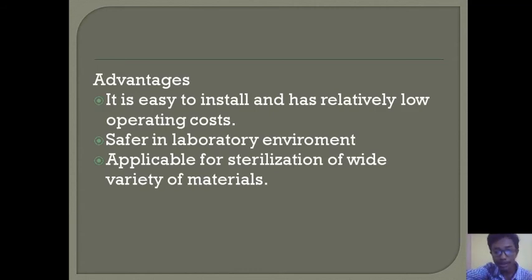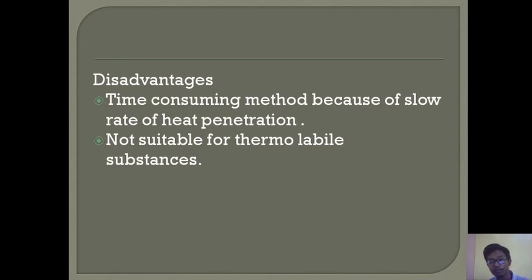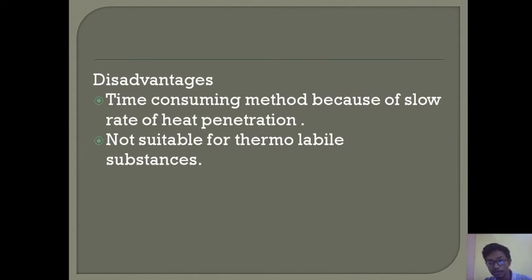Along with the advantages, the hot air oven also has some disadvantages. It is a time-consuming method, requiring up to 2 to 3 hours for complete sterilization of glassware and different kinds of materials. It is not suitable for thermolabile substances — those substances that cannot withstand extreme heat or pressure are called thermolabile substances, and the hot air oven is not suitable for them.